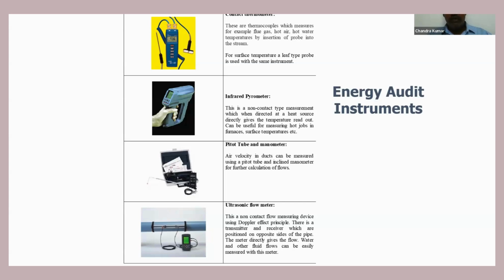Finally, we have the ultrasonic flow meter, typically used for measuring water flow. You have two probes, one sending the signal and another receiving it. This receiver and transmitter have to be placed on the pipeline. Generally for GI pipelines, you need to apply a gel so that it gives a proper signal to help us measure.